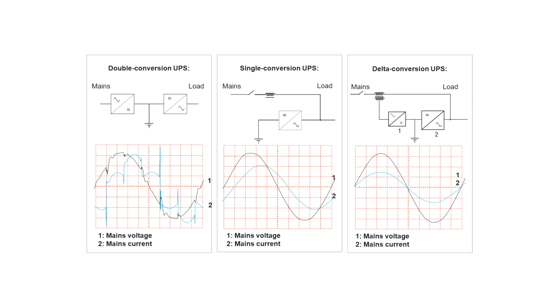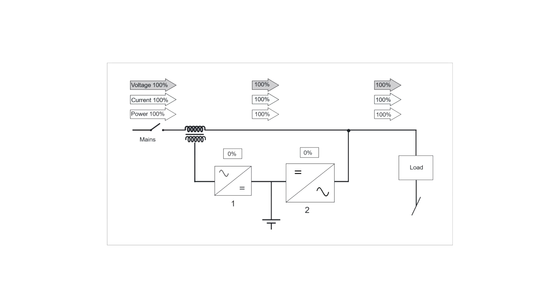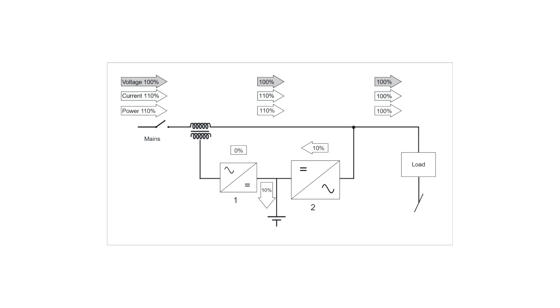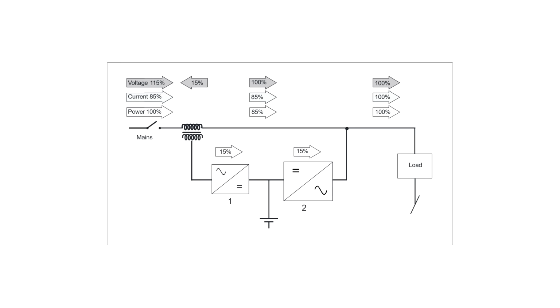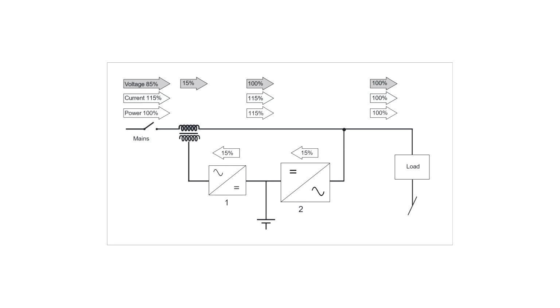Now, the Silcon is a delta conversion UPS, and that involves two converters, both of which can convert DC to AC or AC to DC - they're both bidirectional. You've got your main inverter, which can take the battery supply and power the load from it. And you also have the delta inverter, which regulates the supply that goes through to the load side of the main inverter. It can do this by basically adding or subtracting power from the input, hence the delta is the change.